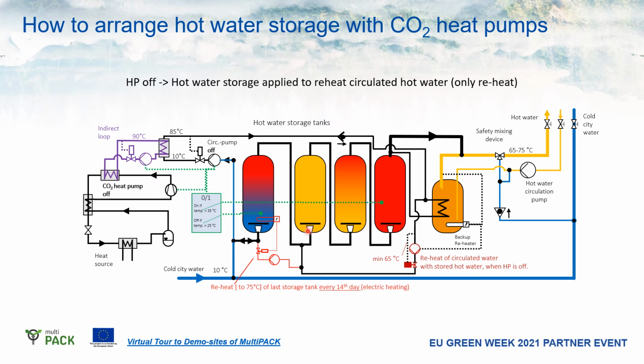So by doing so, we are reducing the temperature slightly in the tank. However, we can utilize the heat from the heat pump to do the reheating. We don't need any electric backup heating. And when there is enough demand, or the tanks are beginning to empty, or there is a lot more cold water, then the heat pump will start again, and we can stop this pump, and it is normally reheated by the produced hot water all the time.